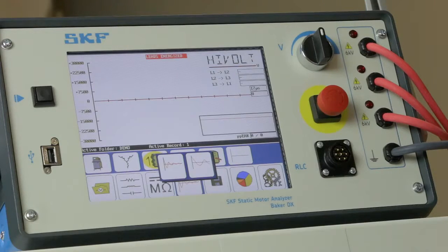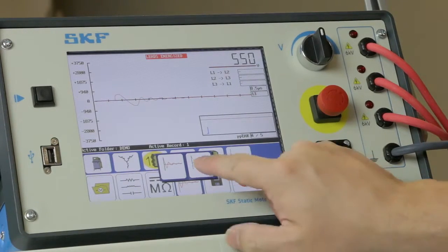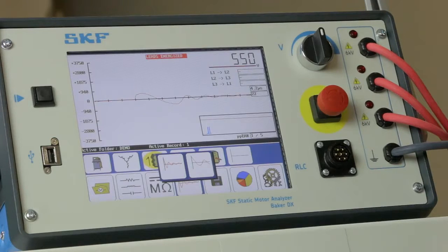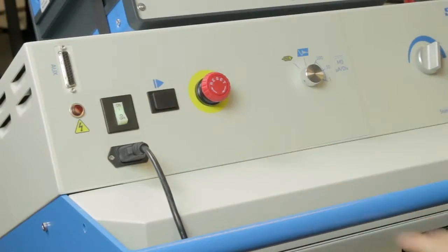Slowly increase the voltage knob until the surge wave can be seen, and then adjust the horizontal scale so that the waveform is shown across most or all of the screen. Slowly and continuously raise the voltage to the desired test value, in this case 14,000 volts. Turning the knob smoothly minimizes the effects of ramping on the pulse-to-pulse EAR. Release the push-to-test button or the foot switch.